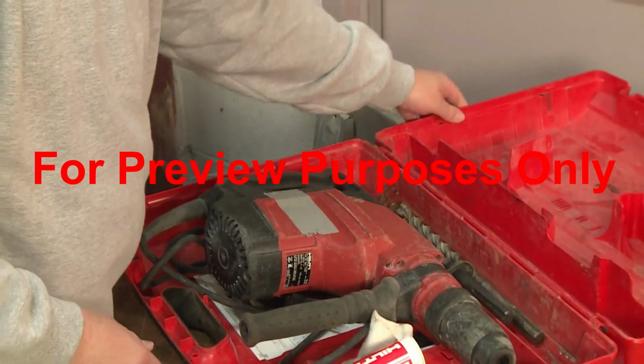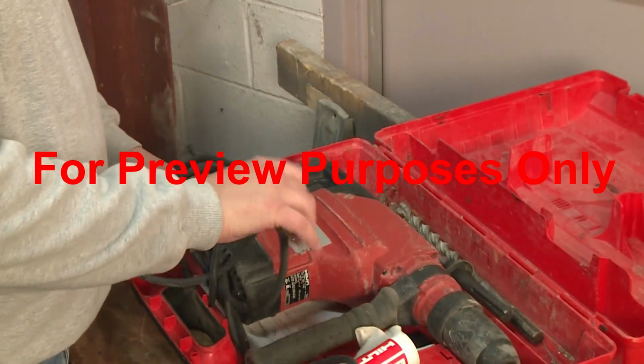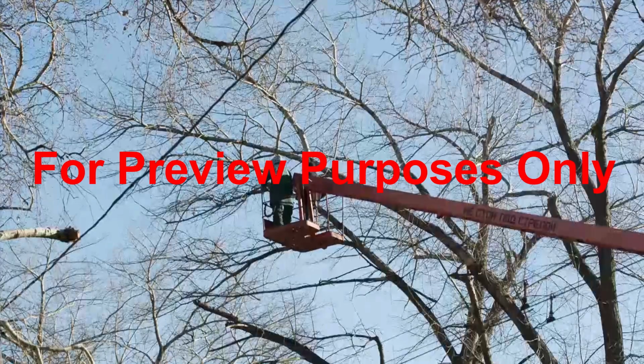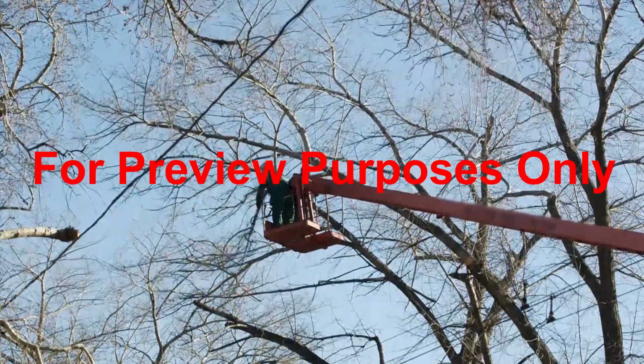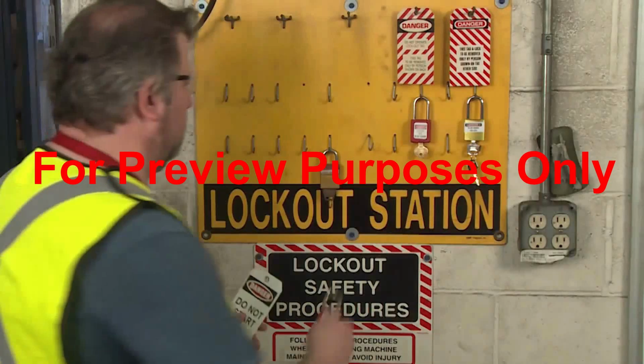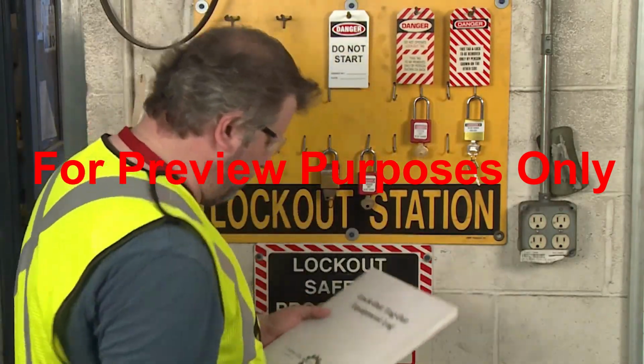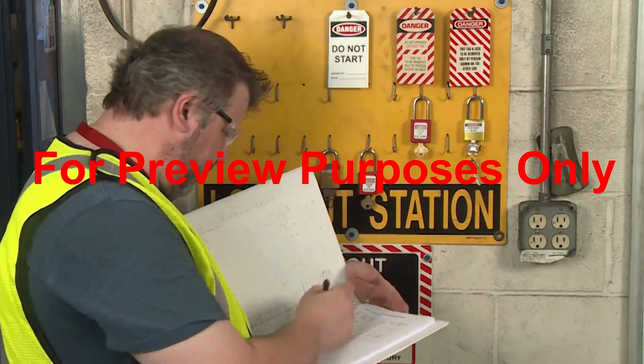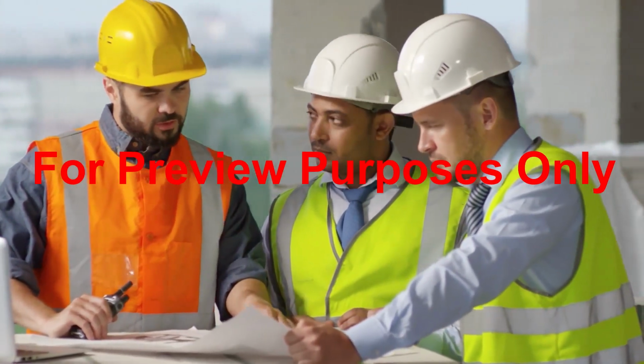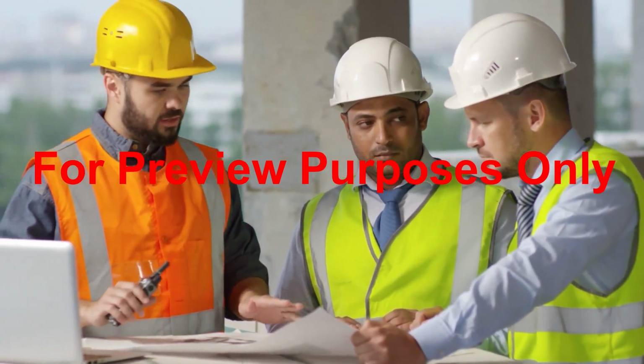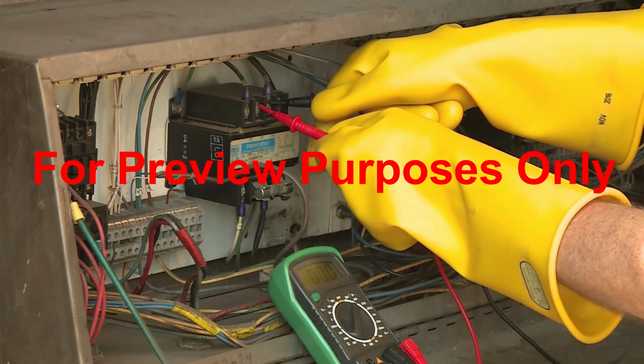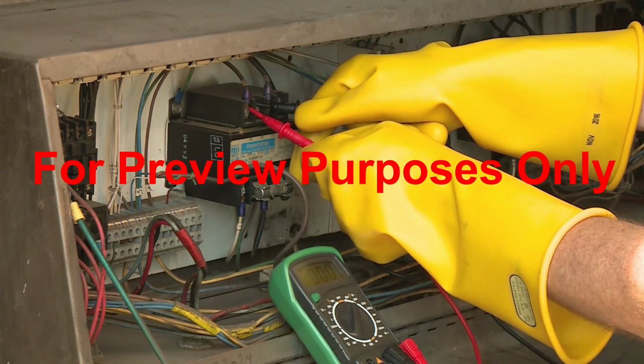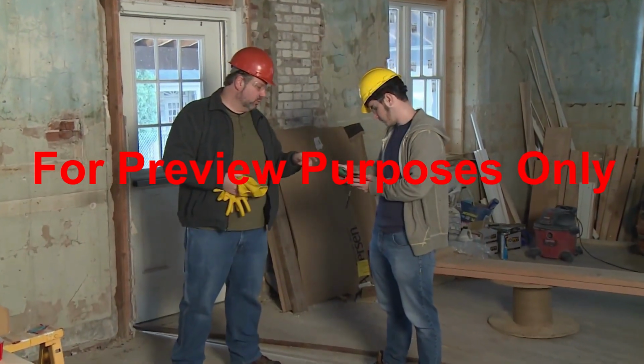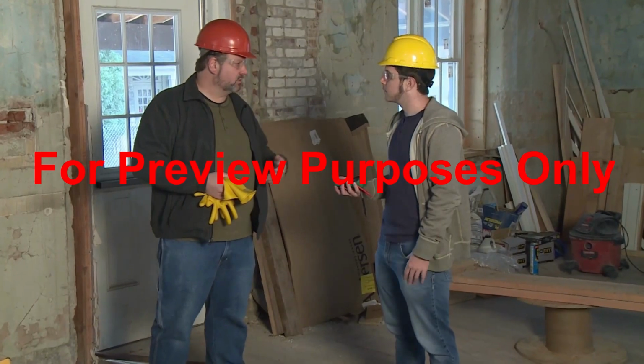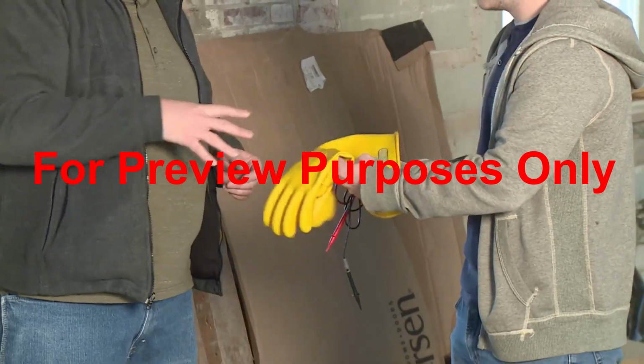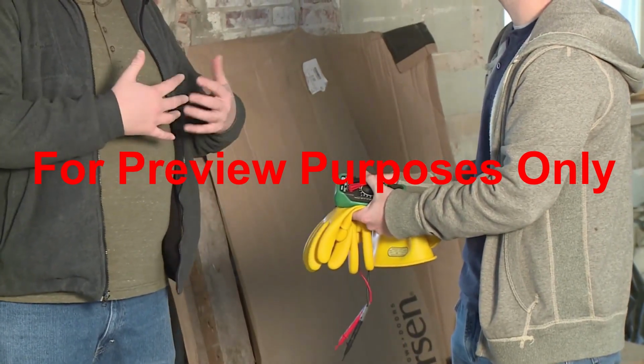The standards also require employers to ensure that portable electric tools and cords are properly used and maintained, take precautions to reduce electrocution hazards when work is performed near overhead power lines, and ensure that lockout-tagout procedures are followed when workers are servicing electrically powered equipment. The OSHA standards also emphasize an employer's responsibility to provide training for all employees on the electrical hazards they can encounter, as well as the equipment and safe work practices they should use to avoid those hazards. Finally, employers should supply their employees not only with personal protective equipment that is appropriate for the electrical hazards on their job site, but also with training on how to use, inspect, and maintain that equipment.